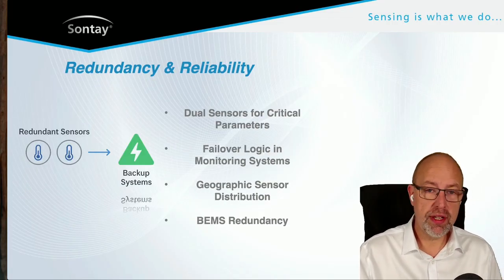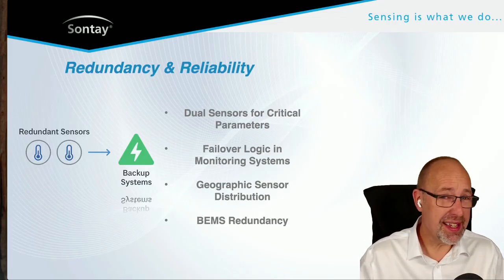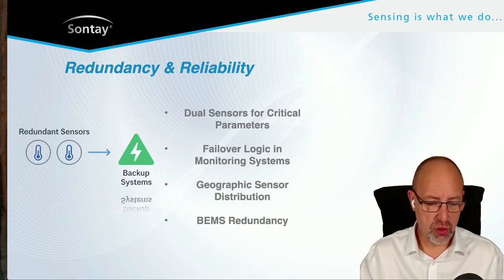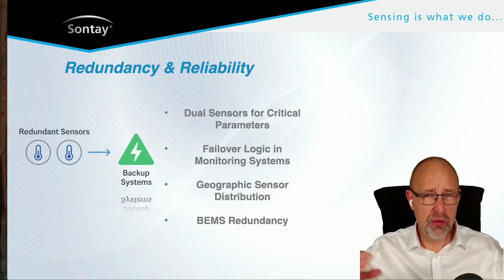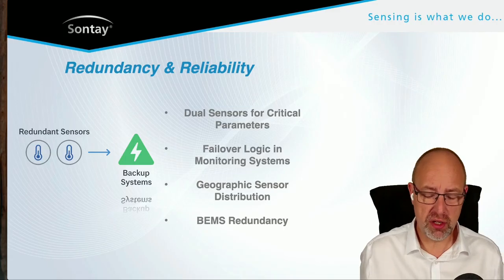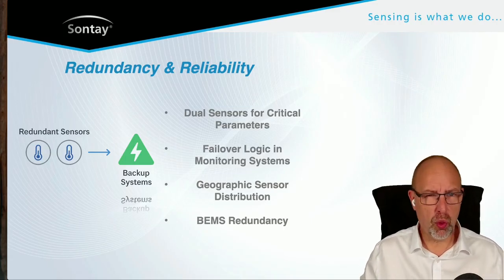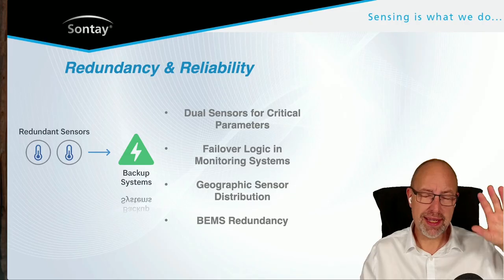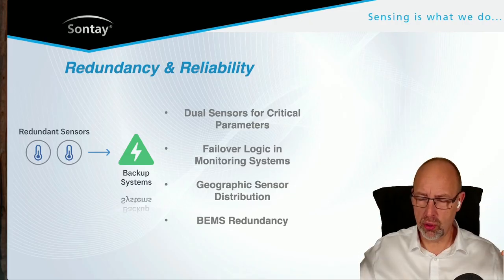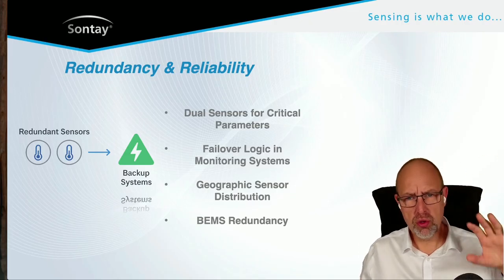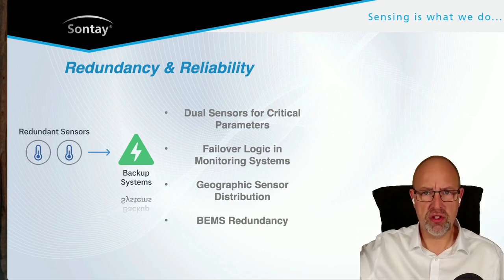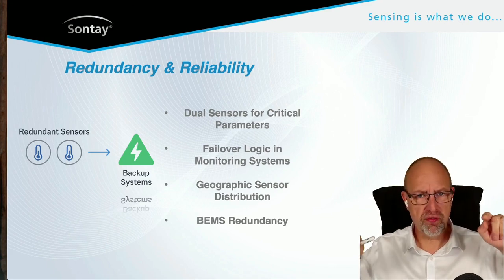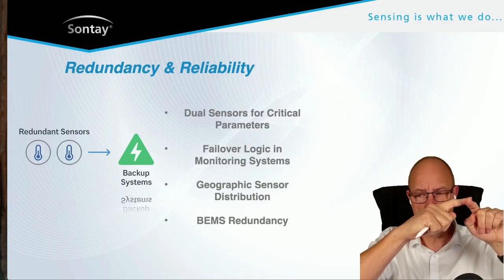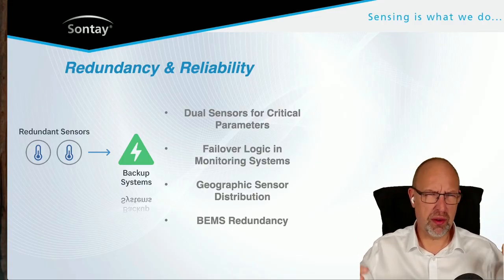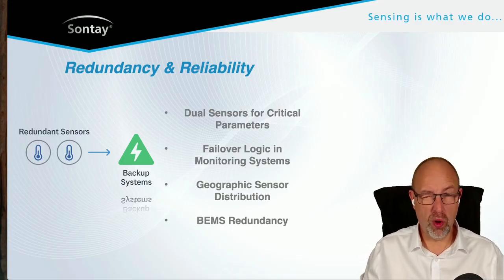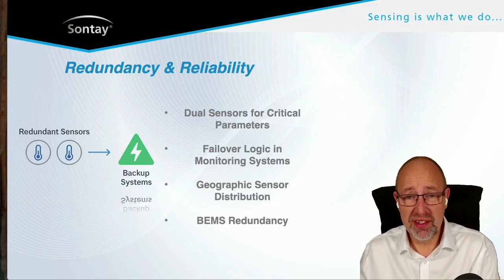On the subject of redundancy, it can balloon very quickly into something very, very unmanageable. I've seen systems before now. When you're setting up a BMS, what you tend to have is a controller with lots of I/O modules. And I've seen systems where they want 2 controllers, and every I/O module is replicated. If an I/O module fails on one, it can actually go to another controller, and then all the sensors are replicated as well. And like I say, it balloons into what is ultimately a quite pointless system.